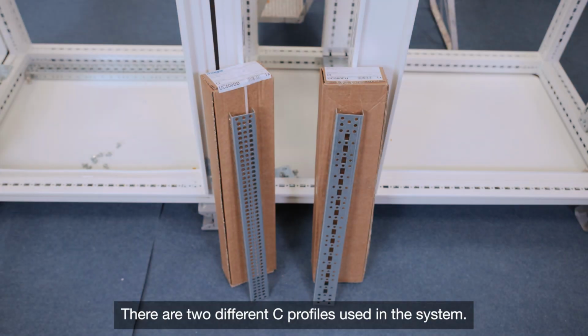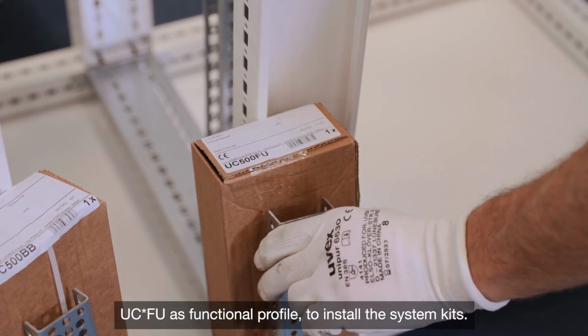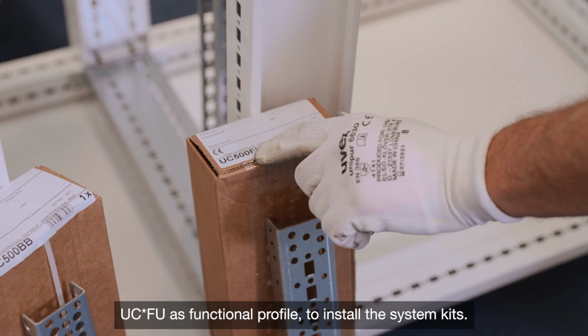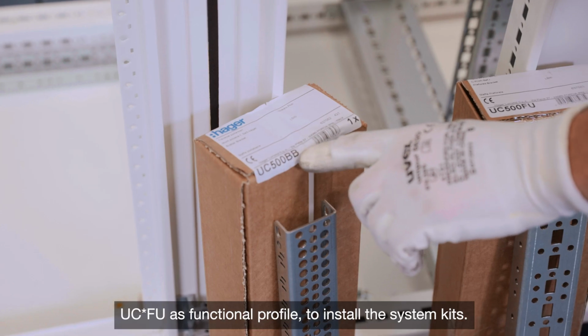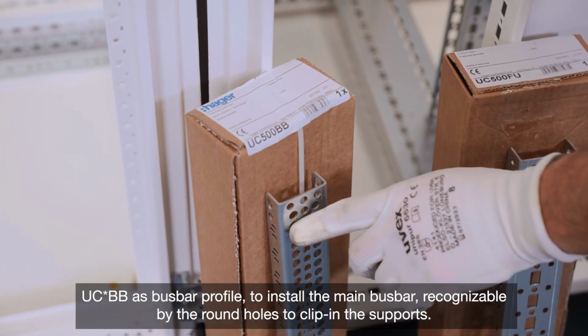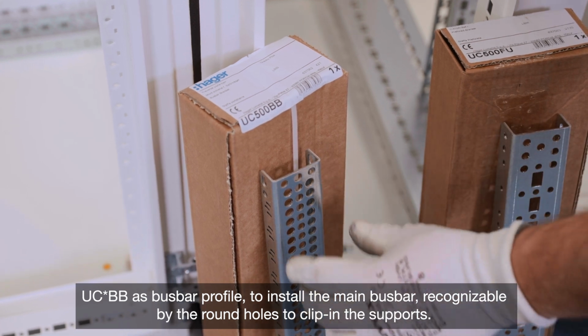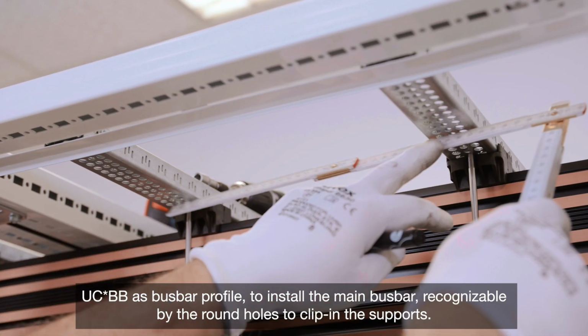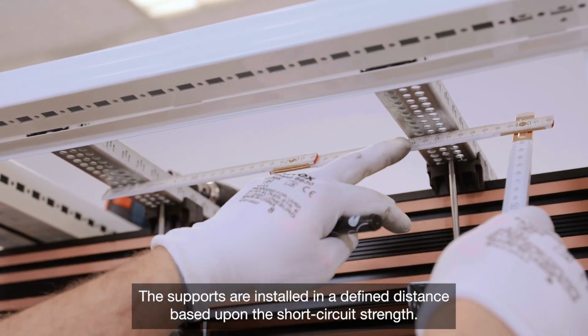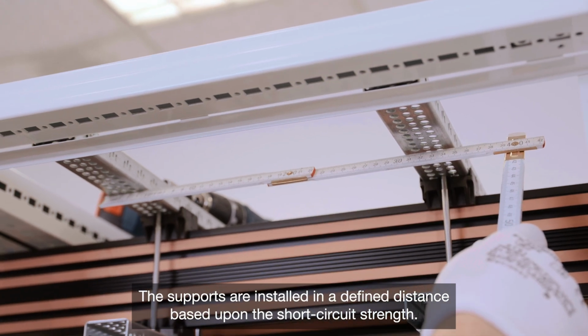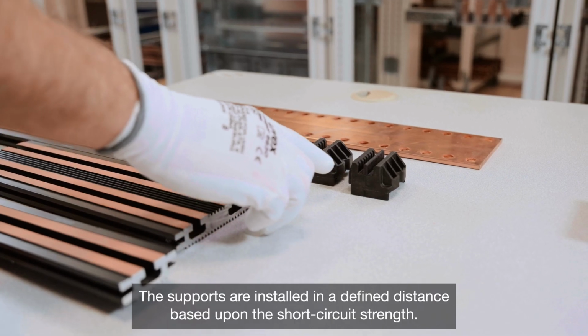There are two different C profiles used in the system. UC*FU is the functional profile, to install the system kits. UC*BB is the busbar profile, to install the main busbar, recognizable by the round holes to clip in the supports. The supports are installed at a defined distance, based upon the short circuit strength.